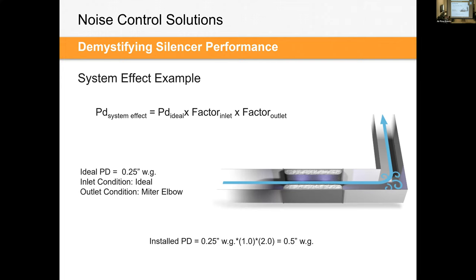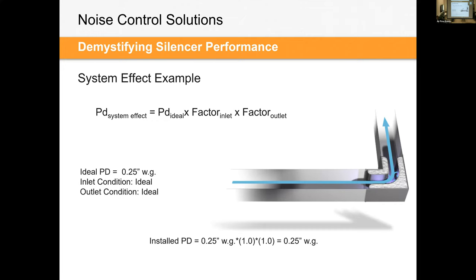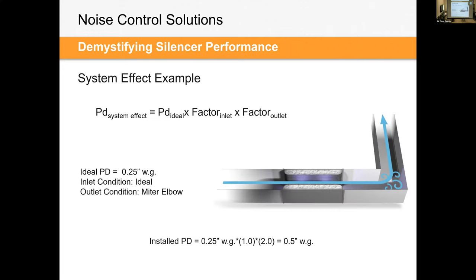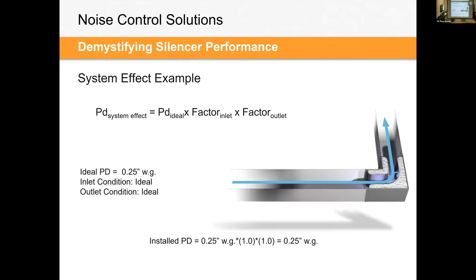And it's important that you understand that, because when you're putting silencers in a duct system, in this case, you're doubling the pressure drop of that device by having this hard right angled mitered elbow at the outlet. What you might do is just put an elbow silencer there. Again, elbows are great where you don't have a lot of space, and maybe it's easier to have an elbow instead of a rectangular one just next to the elbow. And then you're down to that 0.25 inches with an elbow. Ideal inlet, ideal outlet, and I'll just blame the manufacturer. That's a lot easier. That works too.